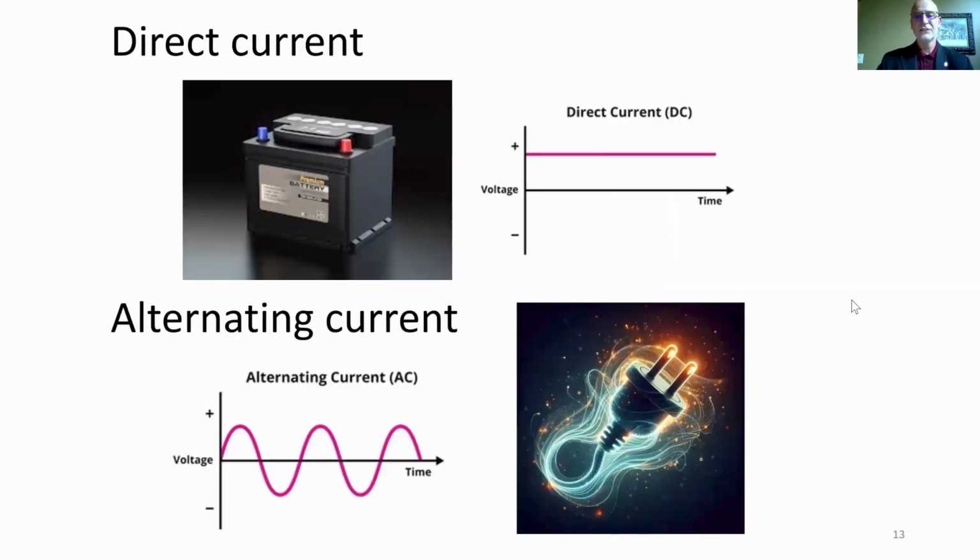So this is direct current. You can think about the car battery. It's a monophasic current. It's not pulsed, so it's on continuously. So one side of the circuit is positive and one side of the circuit is negative. And that can be used for wound healing. So that's pretty good. You would not want to use it for muscle stimulation, and you would not want to use it for pain relief. All right. And then there is alternating current.